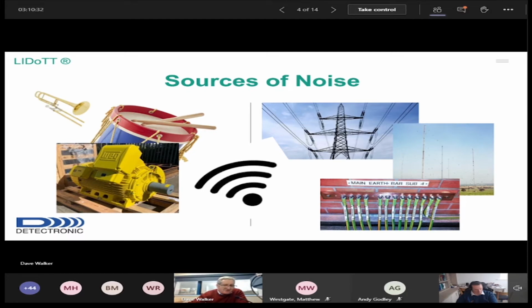But having a good earth supply or a poor earth, as I've just explained, can also create problems. If you've got a rural environment with a very poor earth supply, and you've got noise penetrating around the area, it's very likely that if you've got a mains powered piece of equipment, you could have noise coming back up through that earth and affecting a level transmitter or a velocity transmitter. So we have to be appreciative of earth supplies when dealing with EDMs and mains powered equipment. Portable equipment, battery operated, tends to overcome that because you're not connecting to earth, so it's isolated from the earth itself. It's what's called double insulated as well, so we don't have the same problem there.